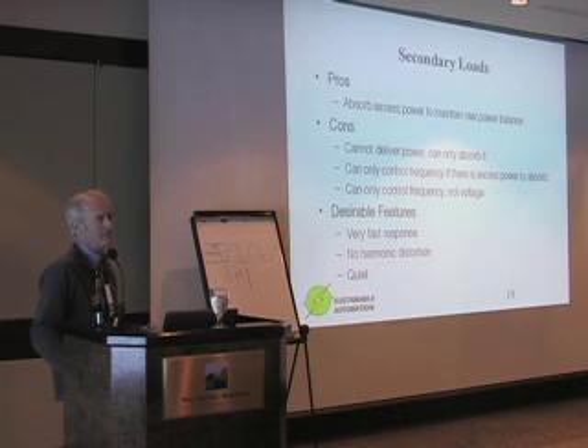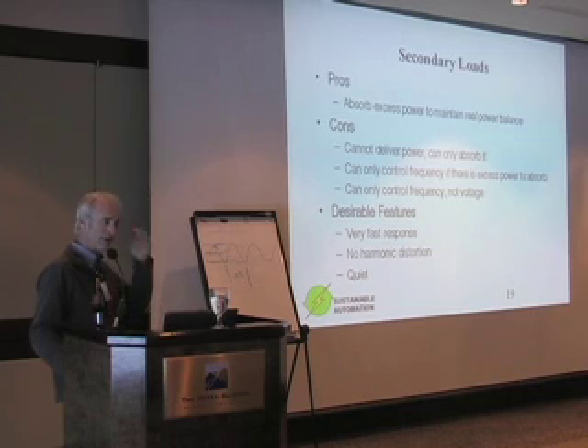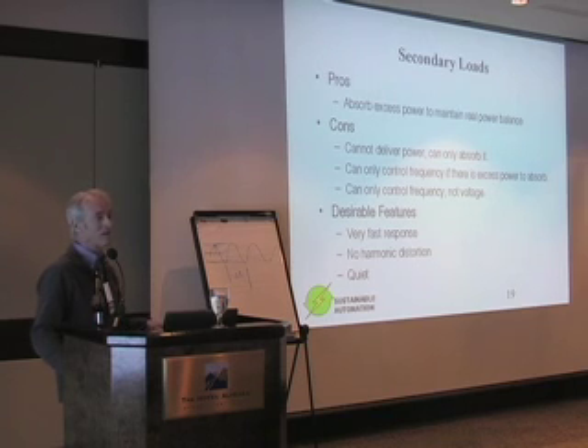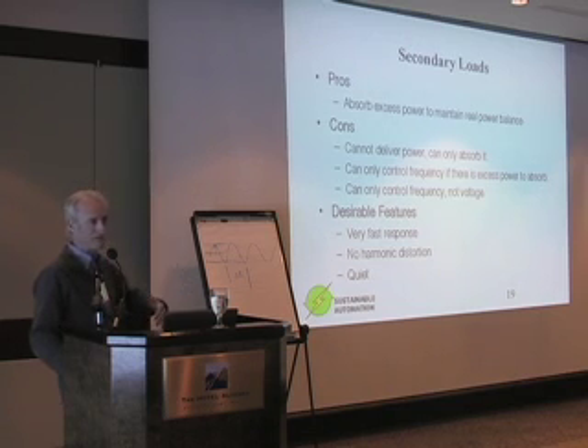What makes a good secondary load, as I said, is its ability to respond very quickly. And the electric boiler with rapidly switchable elements can do that. Our latest generation of secondary load control basically has about a 5 millisecond response time. So it's much faster than the diesel speed control, and when you add it to the system, it can smooth out the frequency fluctuations so that the diesel essentially sees a pretty steady load, and it operates quite comfortably. You don't hear a lot of surging in frequency that you sometimes hear when you put a wind turbine in parallel with the diesel, when the wind turbine starts to jerk the frequency around.